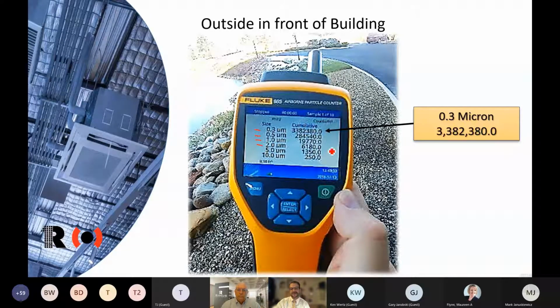2.5 is the one that the EPA talks about a lot. But 10, they say 10 is about the smallest particle a visible eye can see, and then everything else here is really essentially invisible. So you're measuring invisible particles. And in this particular project, what we look at is these 0.3 particles, because these are the small particles that the HEPA scrubbers are designed to remove. But any of these particles from 1 to 3 are particles that the virus can attach to.